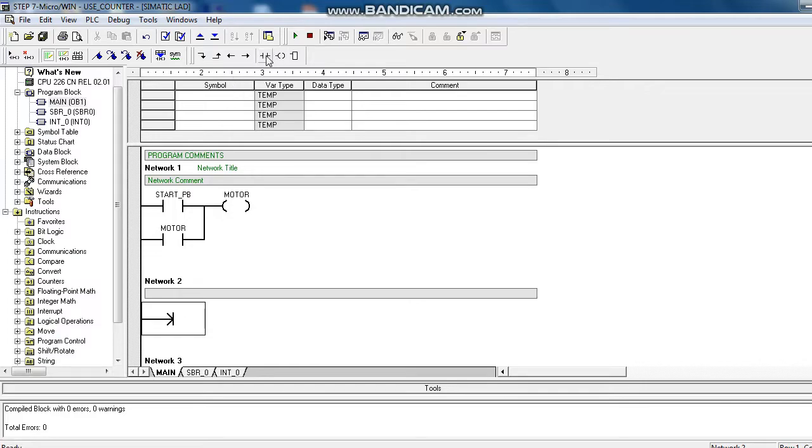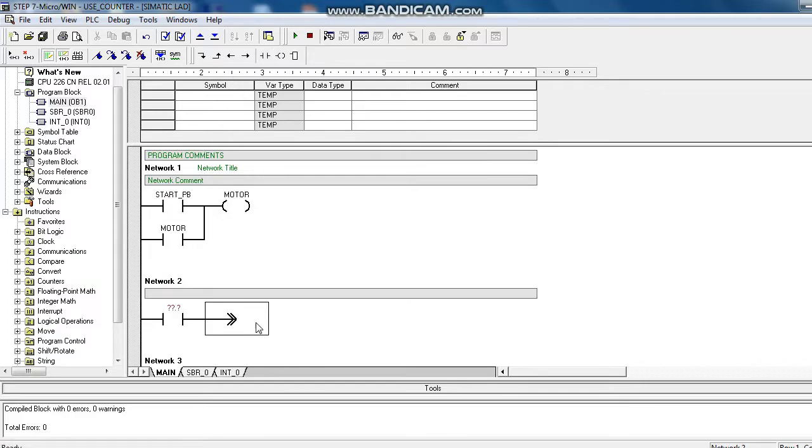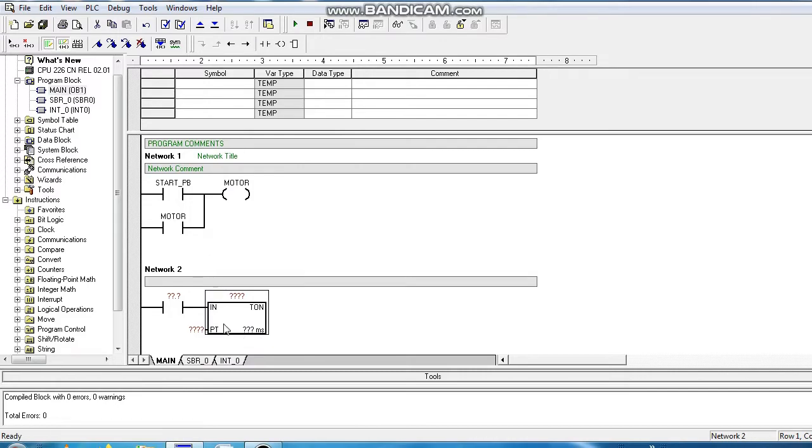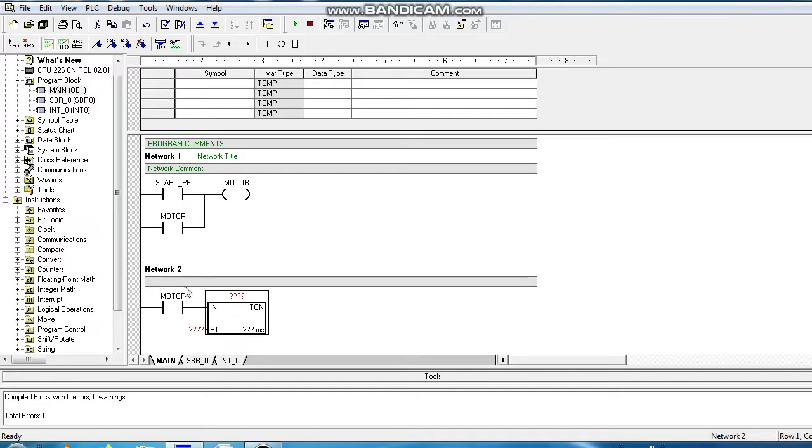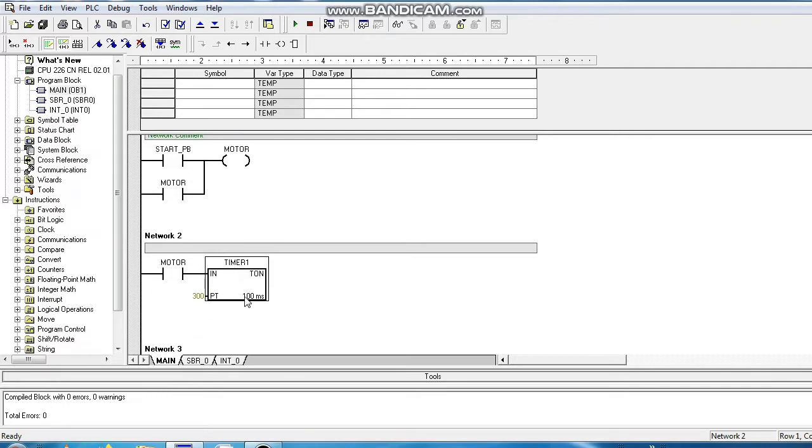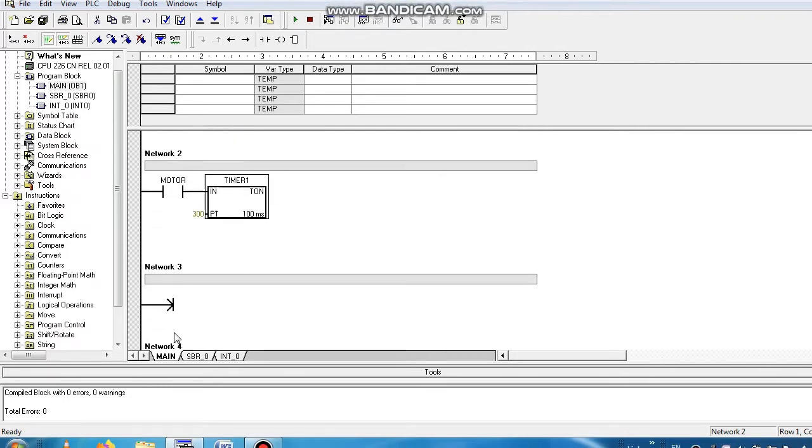Now here we use the timer. You can find it easily by typing TON. When the motor gets power, the timer will start. So we use the motor contact here. It is named T37, timer 1, we use 30 seconds. After 30 seconds motor will start again.